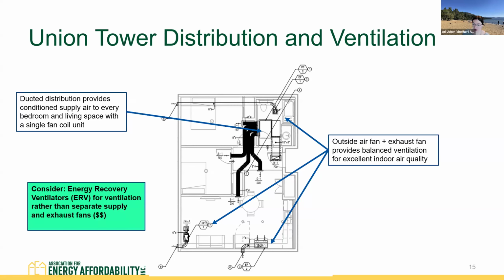And one consideration for energy efficiency would be an ERV. An energy recovery ventilator is a single piece of equipment that has the supply and the exhaust fan in one cabinet. And additionally, it introduces a heat exchanger into the ventilation system. You're able to pass the 2 air streams over each other, and this allows you to both temper the incoming outdoor air, and it'll also allow the heat pump to run a little bit less because you're not losing that conditioned air that you've just heated up or cooled down through exhaust.